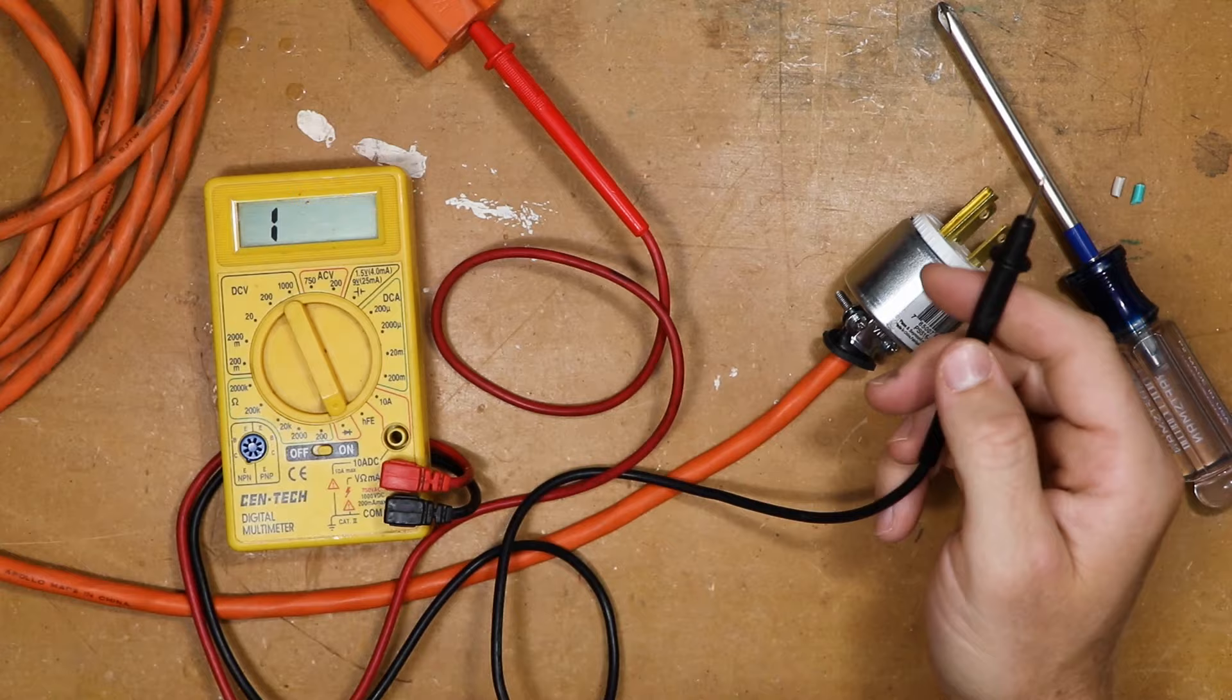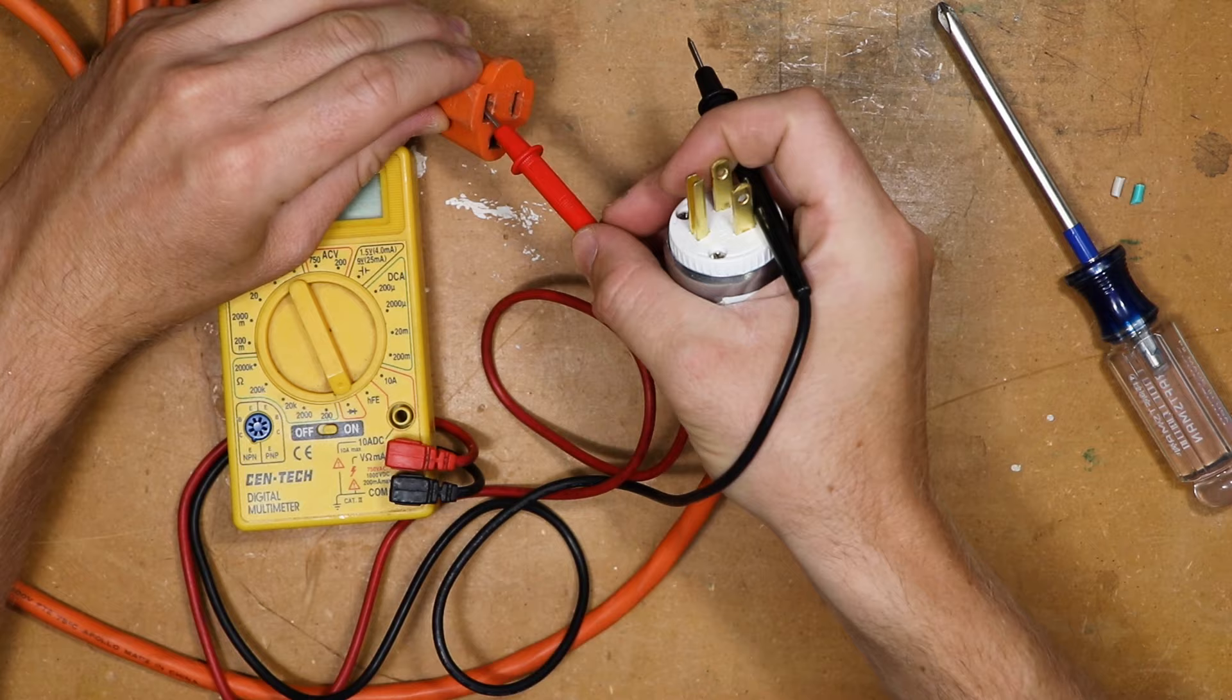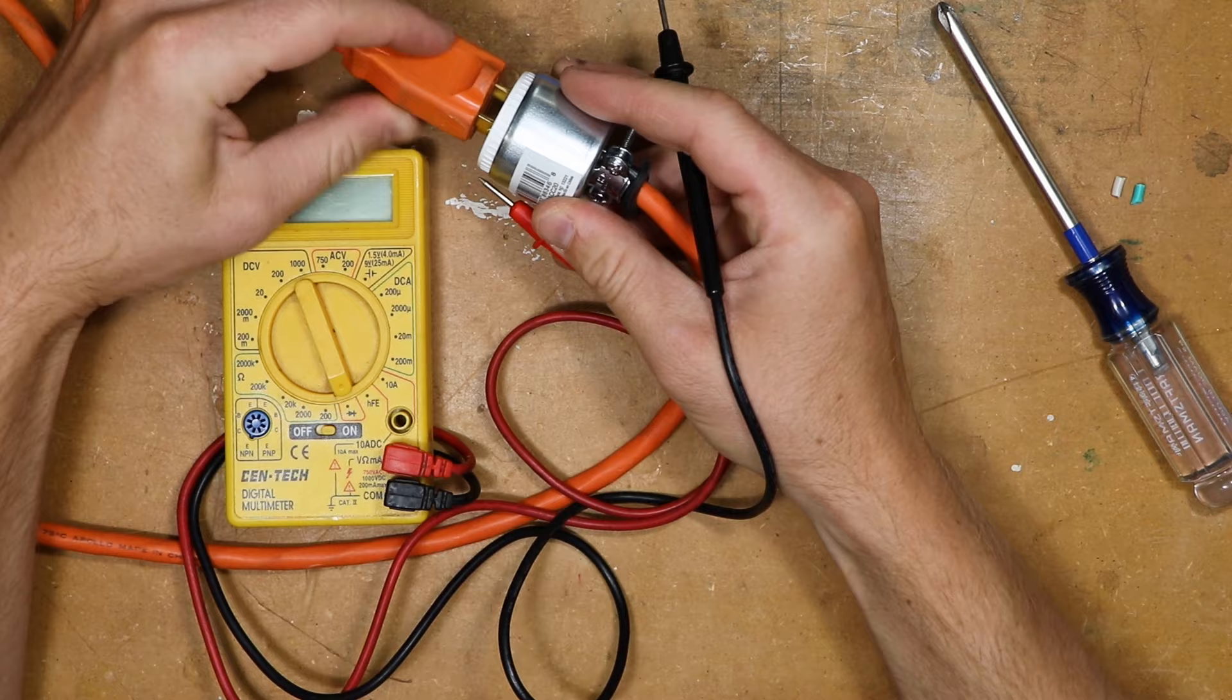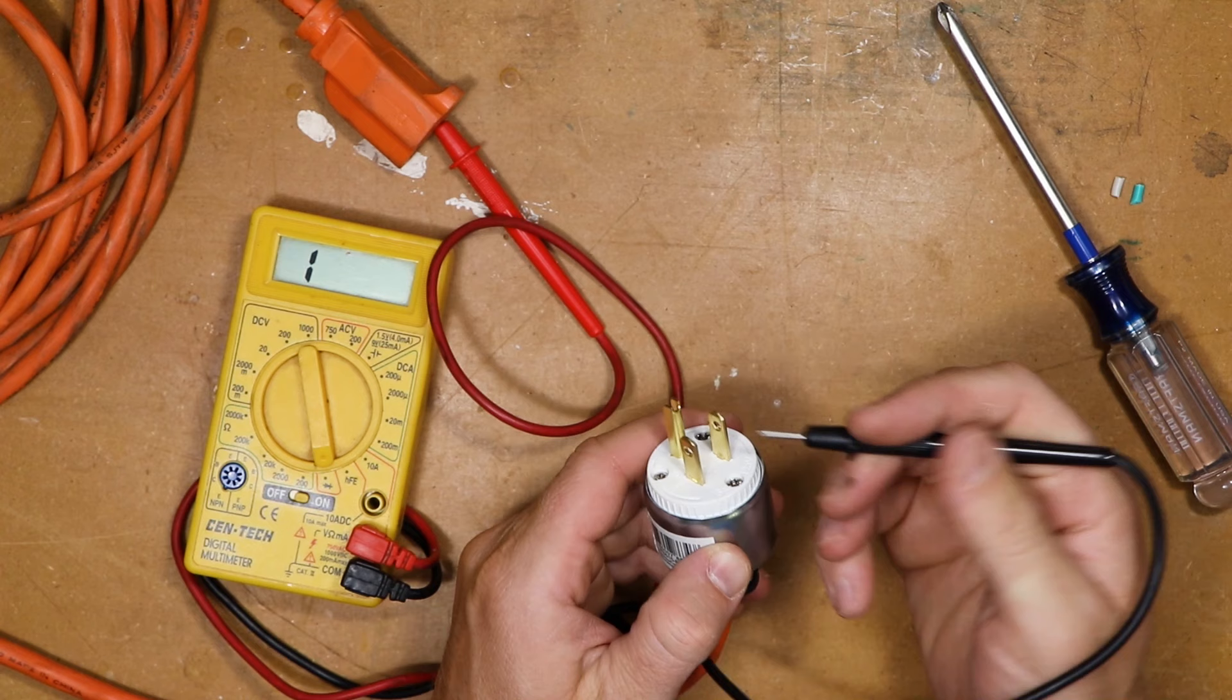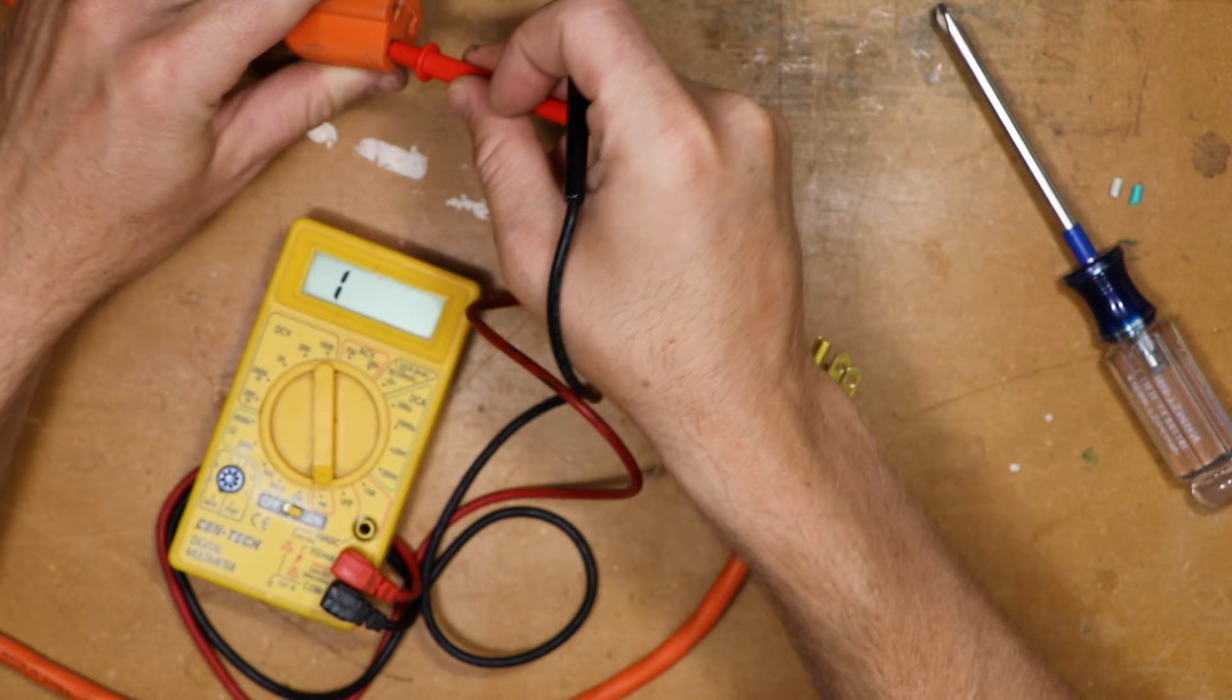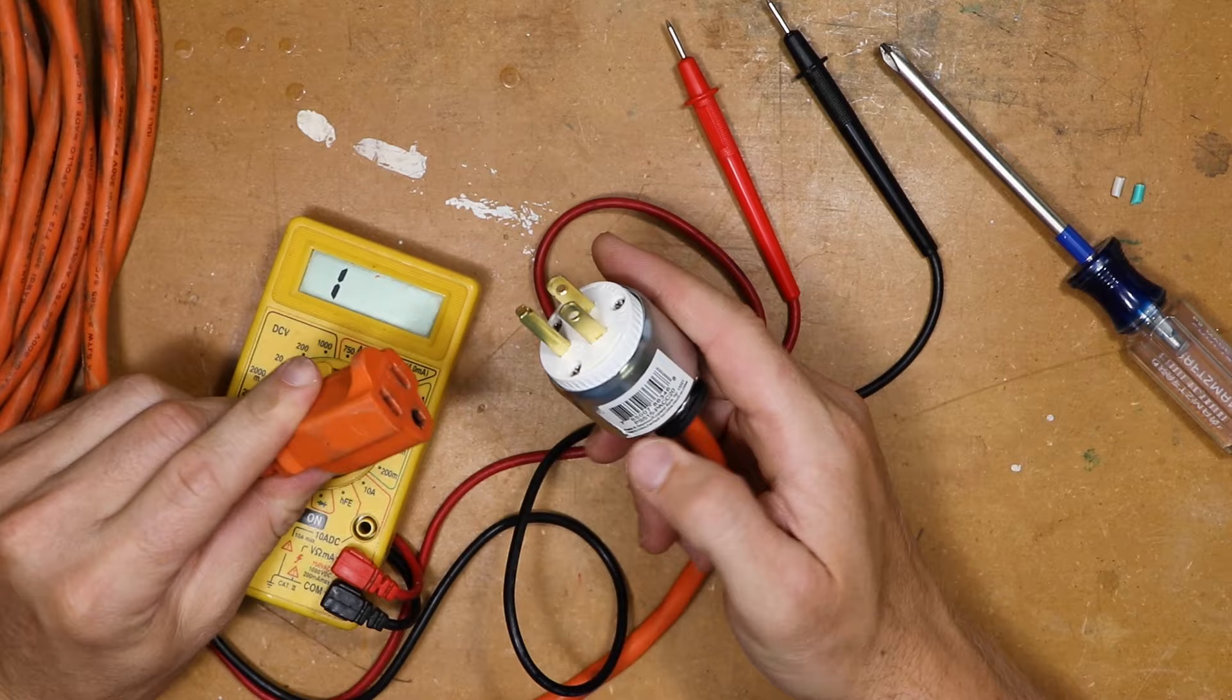The first thing I'm going to do is stick it into one side. I'm going to stick it on that side. And then over here, you just want to make sure that these line up correctly visually. So if I'm in this first big hole here, then I'm going to need to check this left side of the plug this way. And boom. So we know that the wire is actually creating a closed circuit when I do that inside here. And we could do that with each of them. So our two hot and neutral are working quite well. And the ground is a little more difficult to do because it doesn't really wedge in there. So I'm going to have to find a nice contact, hold it with one hand and then touch this with the other hand. And there we go, we got good continuity for our ground.